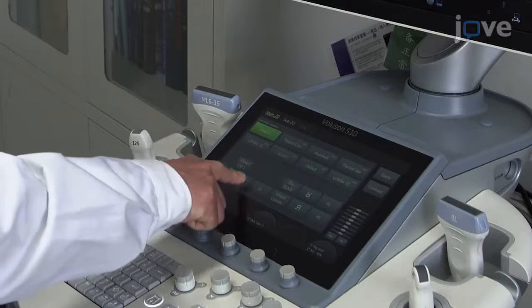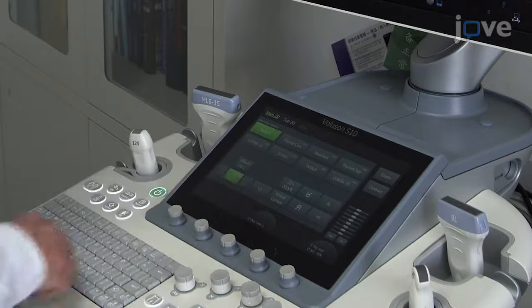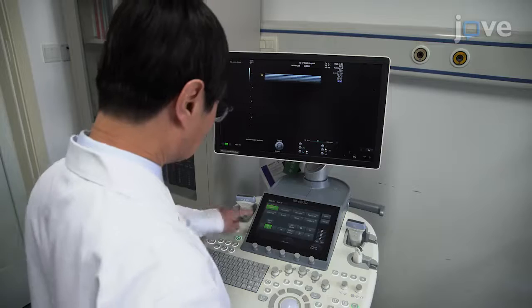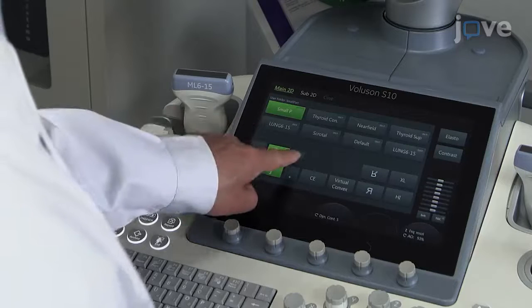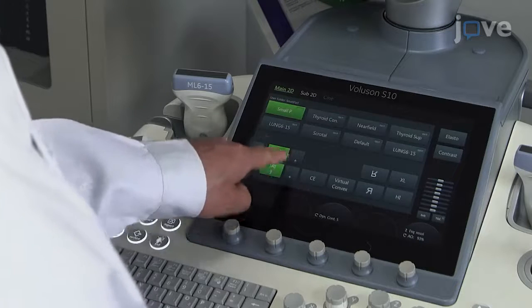Click the Speckle Reduction Imaging button and select a level of 2 to 3 to reduce the speckle noise. Turn on Cross-Beam Reduction Imaging and select a level of 2 to improve the contrast resolution. Then select Fundamental Imaging for sharper A or B lines.